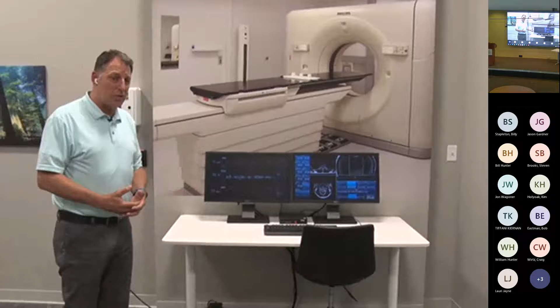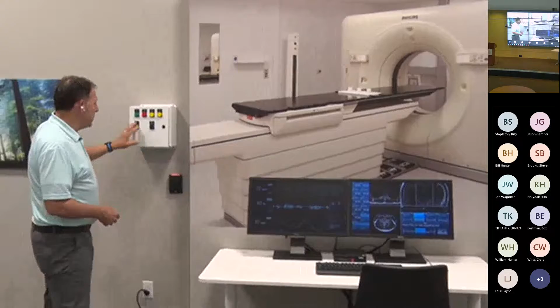And so what we would typically do is install a UPS between the electric power supply and the MRI itself. What that will do is clean that power up so it's easy for us to get good image acquisition. And we've also partnered with Philips, the maker of this MRI, to develop this remote alarm panel so that the technician can see the green light means go, and it's the right time to acquire the image for the doctor or whoever is looking at the MRI from the patient.